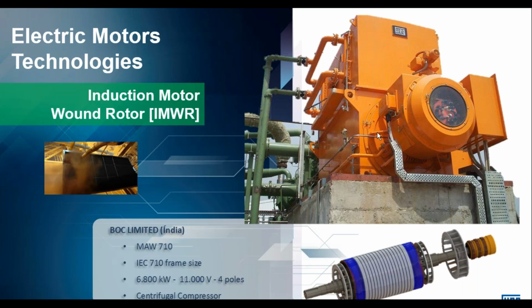But the issue here was less so the replacement of the brushes and more the amount of dust buildup in the slip ring compartment. They were installing special filters to capture the dust, and every few days they needed to clean the dust out of the filters. I'm going to demonstrate on a video. This was after a few days of carbon dust buildup blown out of the filter installed in the slip ring compartment.